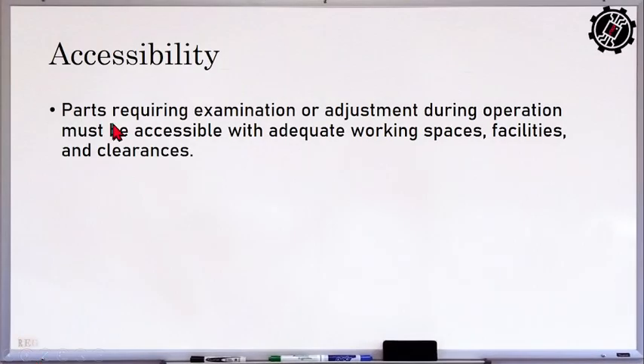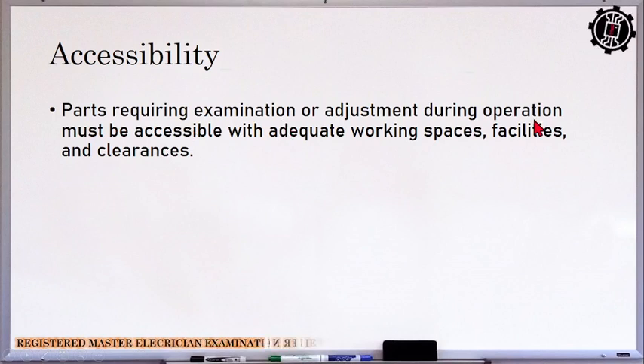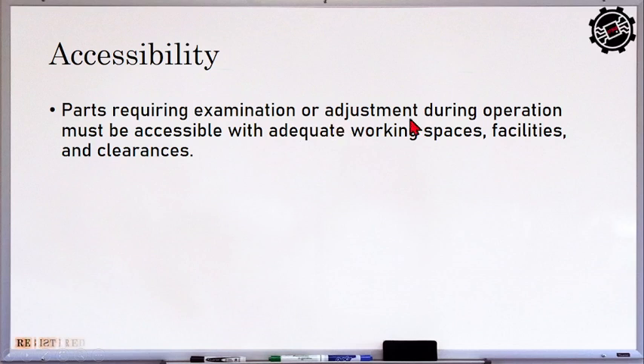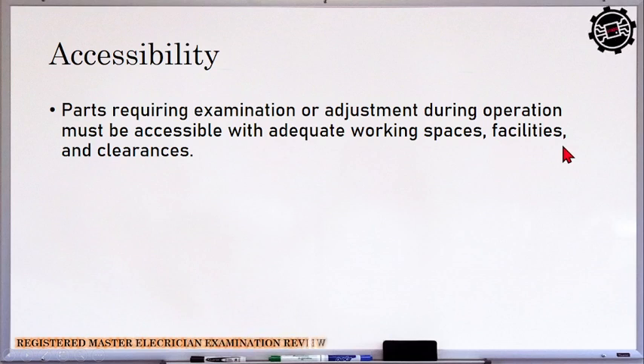Okay. Next, we have accessibility. So parts requiring examination or adjustment during operations must be accessible with adequate working spaces, facilities, and clearances. So if there is part sa ating underground system na kailangan ng examination or maintenance, that is the purpose of the adjustment during the operation, so dapat meron siyang adequate working space na naka-indicate sa ating chapter 1, the proper working space on electrical equipment. Tapos may facilities, may tamang lighting so that maliwanag yung part na kung saan mayroong magmi-maintain o may magtatrabaho. Tapos clearance, may tamang clearance to live parts.